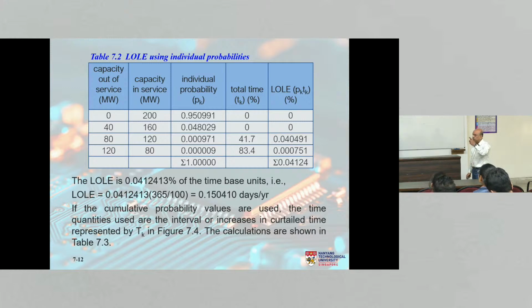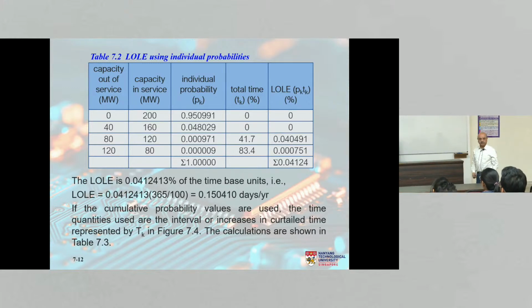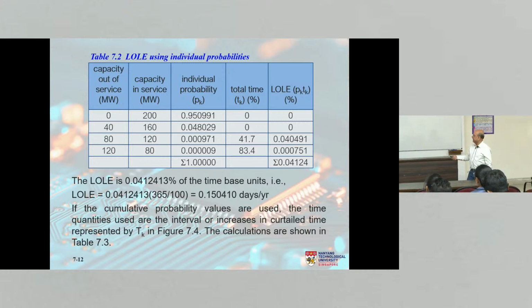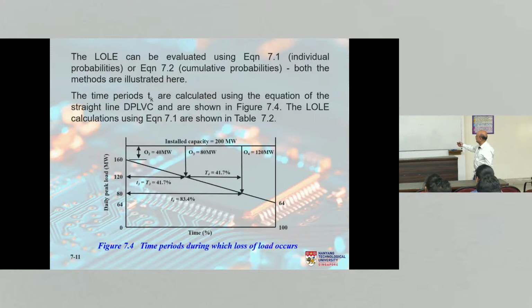Tk for the first outage, meaning no generators out, is 0. Tk for the second case, one generator out, 40 megawatt, is still 0, because we are not losing load. There is no loss of load. Clear? Then the third case, when 2 generators are out, we lose 80 megawatt. Then of course 80 megawatt is here, and this is my load curve, and I'm not able to supply the load for this time T3, small T3, okay?